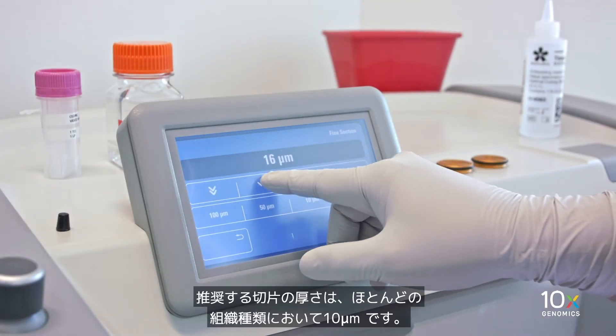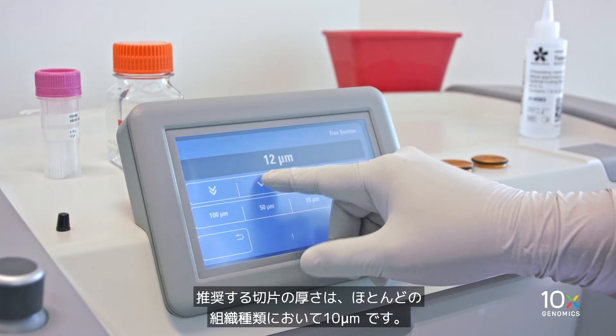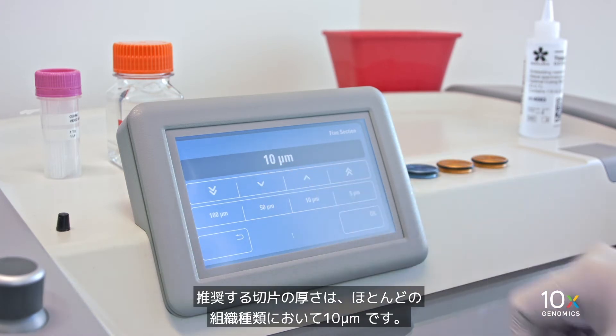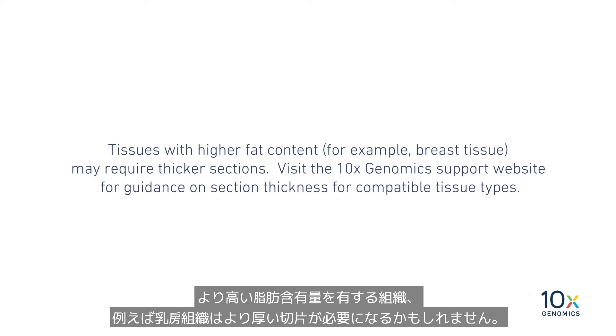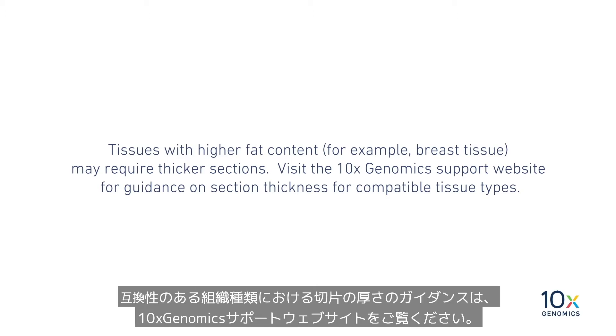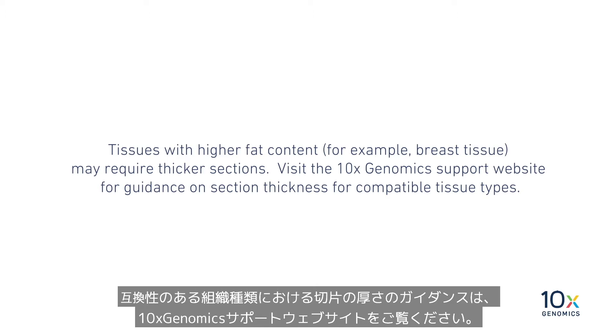Confirm the appropriate section thickness setting of the cryostat. The recommended section thickness is 10 microns for most tissue types. Tissues with higher fat content, for example breast tissue, may require thicker sections. Visit the 10x Genomics support website for guidance on section thickness for compatible tissue types.